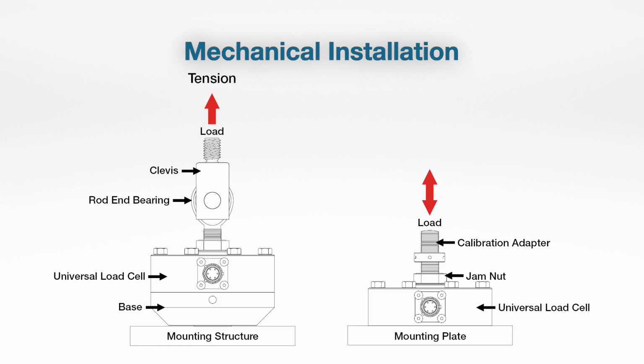Now here's some examples of our LPs. The left one is installed on a base, which is then installed to a mounting structure or some sort of, it may be a hydraulic actuator. And then on the top side, we've got a rod end bearing and a clevis. We typically recommend introducing some rod ends if possible or clevises just to minimize the amount of bending moment that may be exerted on the load cells.